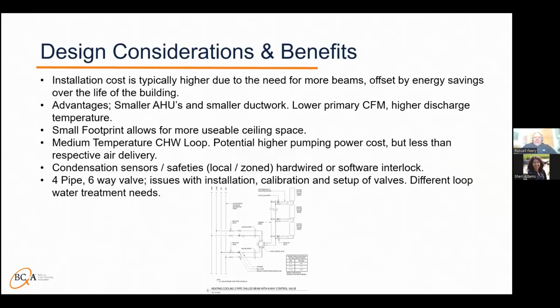Now, some design considerations and benefits. Installation cost is typically a little higher due to the need for more beams, but it is offset in the long run by energy savings over the life of a building. The advantage is smaller air handlers, smaller ductwork. They've got a lower primary CFM, higher discharge temperature, and a smaller footprint allows for more usable space.